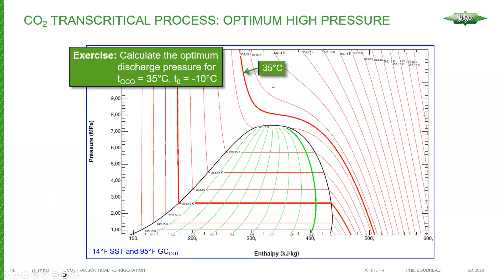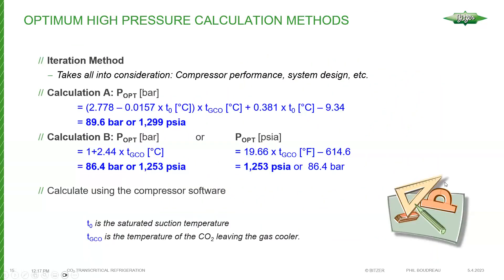Looking at an example with a gas cooler outlet temperature of 95°F (35°C) and an evaporating temperature of -10°C (14°F), we can examine the difference that pressure makes in terms of coefficient of performance. There are different ways of determining optimum pressure. One is the iteration method — the most basic approach is to take a pressure-enthalpy diagram and plot a number of cycles to find where your best COP is.